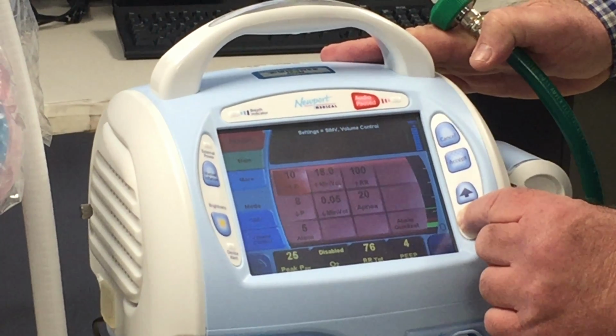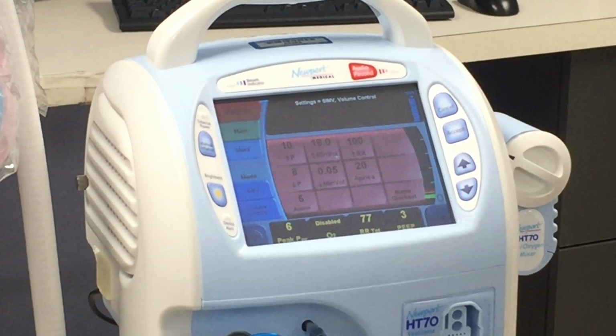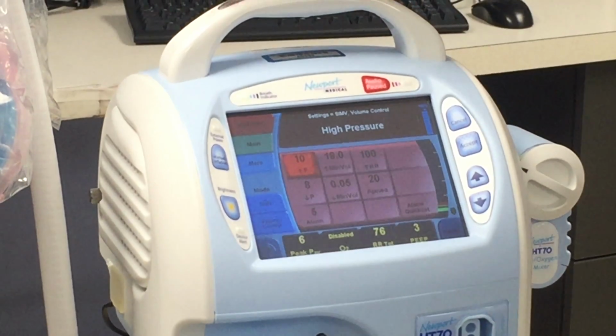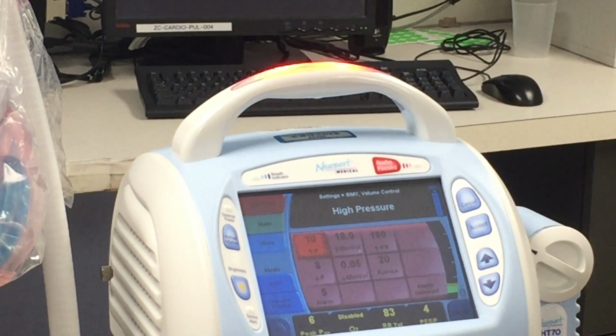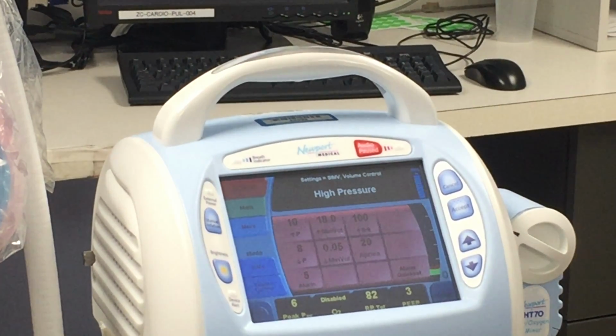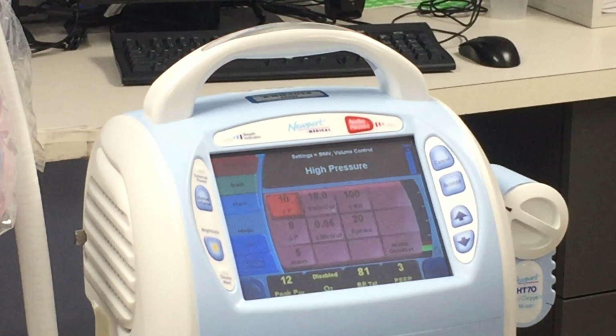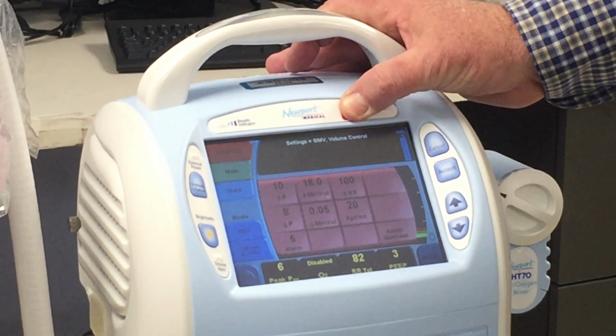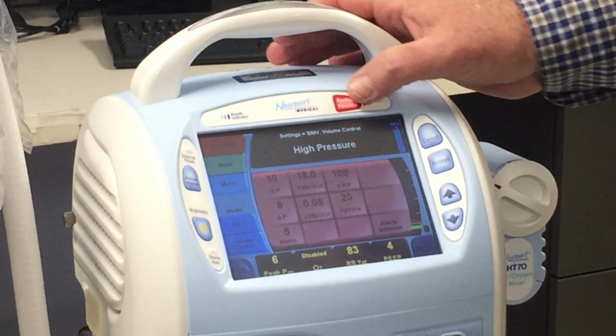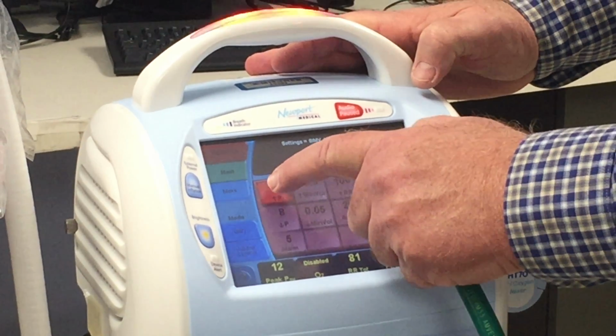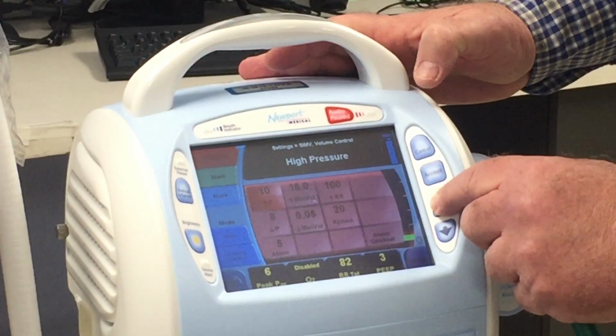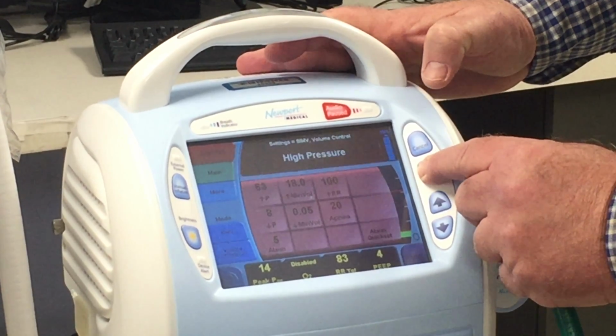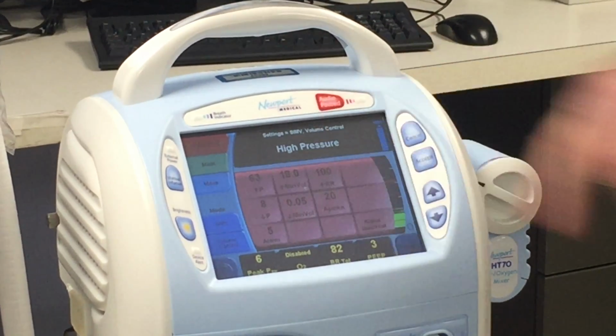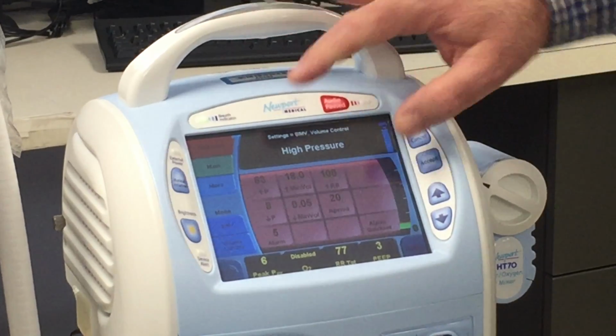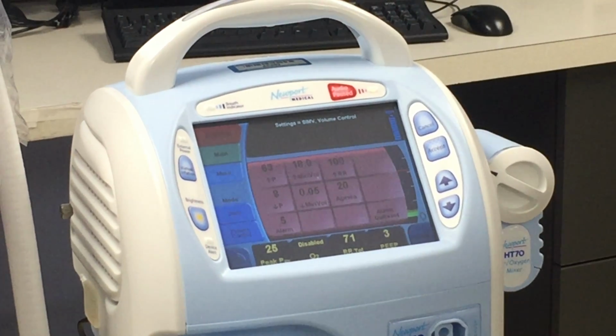what you'll get, let's see here, turn down our, so here's your alarm situation. You can see it. It should be viewable in any position, 360 around the ventilator. Also gives you a visual. It gives you an audible alarm as well. To silence that, hit your patient silence, and then go ahead and make it. You can see it's a darker red, so you know which one to change. And you can see you'll still get a visual here even after it resets. And to reset any alarms up here, you just hit your reset button. Okay.